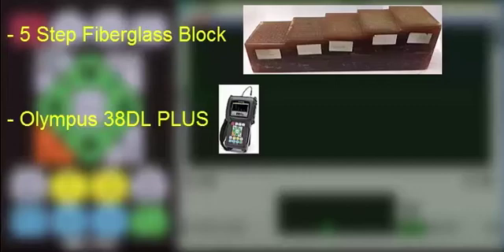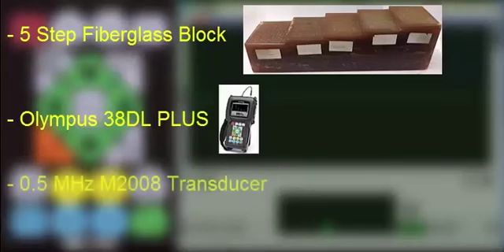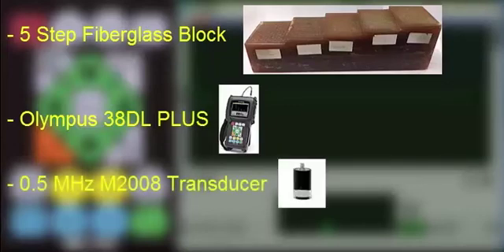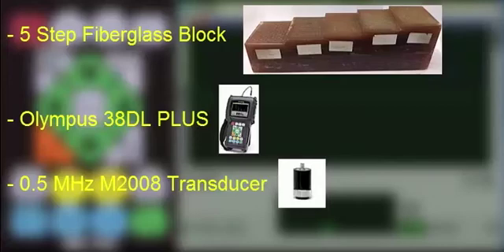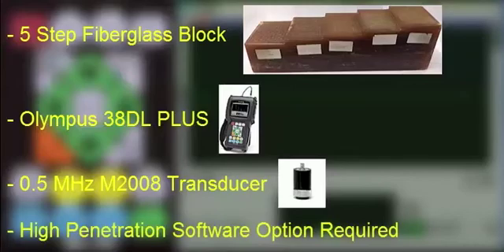In order to penetrate this thick of fiberglass, we will need to use a half megahertz M2008 high penetration transducer. Since the frequency of this transducer is lower than 2.25 megahertz, it is considered high penetration and therefore the 38DLP-HP software option would be required.